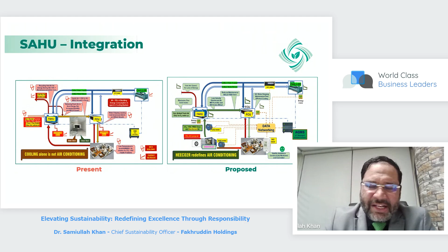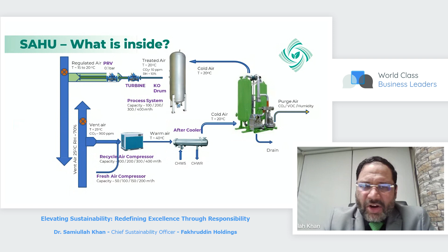We take the ambient air and we compress the air to about 7 bar pressure. We take the air from inside the building, which is about 1000 ppm CO2 with the contaminants, compress it again to about 7 bar, cool the compressed air, and then extract the carbon dioxide using the pressure swing adsorption technology. So the air which goes into the building goes in at 0 ppm CO2, and then based on the requirement of the building, the air enters into the building. So this is the schematic of the process.